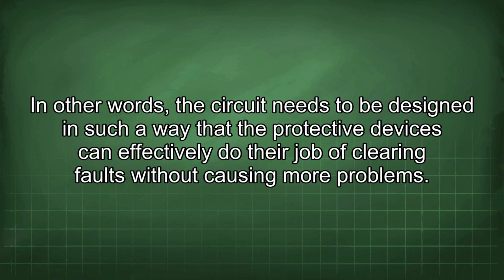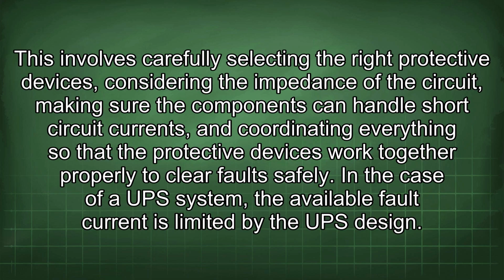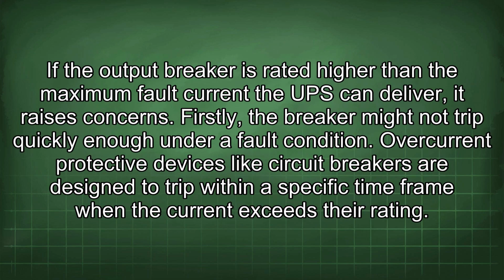In other words, the circuit needs to be designed in such a way that the protective devices can effectively do their job of clearing faults without causing more problems. This involves carefully selecting the right protective devices, considering the impedance of the circuit, making sure the components can handle short-circuit currents, and coordinating everything so that the protective devices work together properly to clear faults safely. In the case of a UPS system, the available fault current is limited by the UPS design. If the output breaker is rated higher than the maximum fault current the UPS can deliver, it raises concerns.